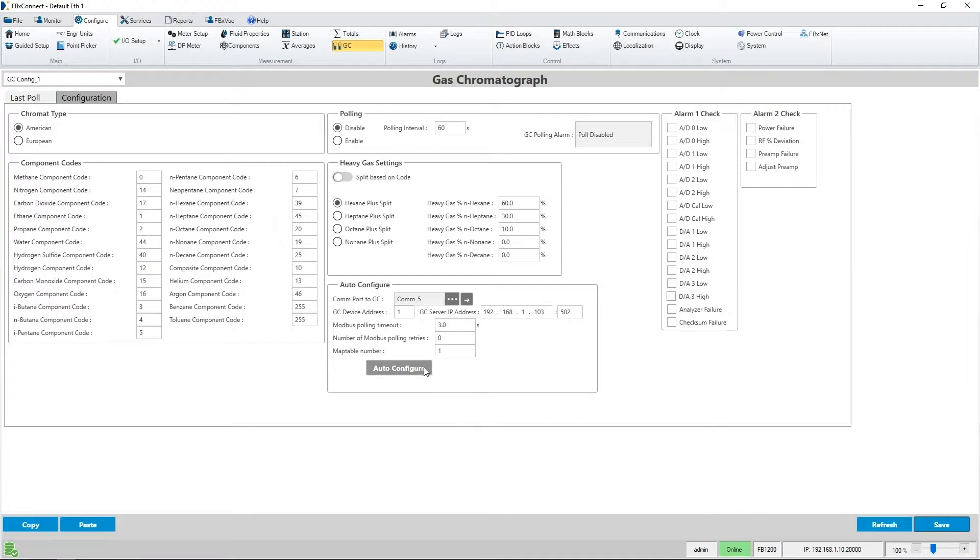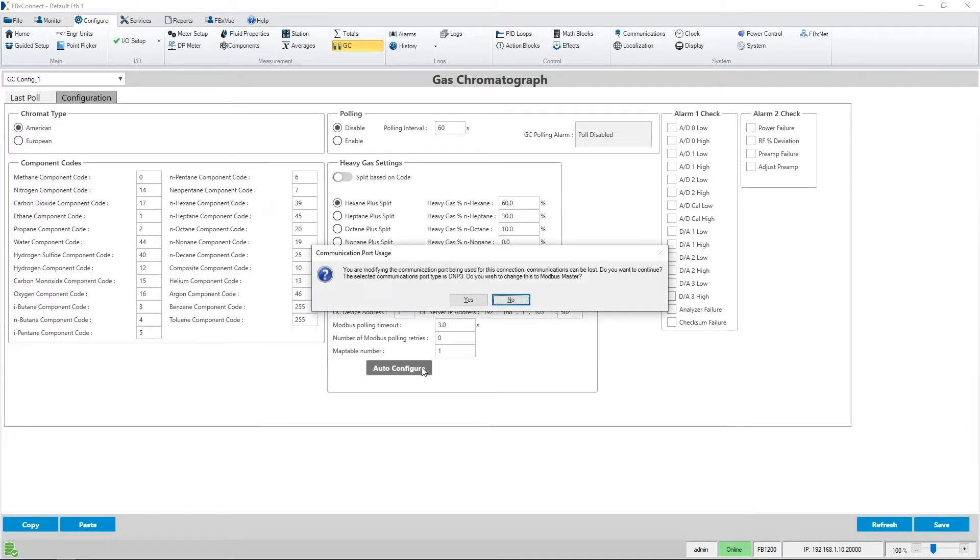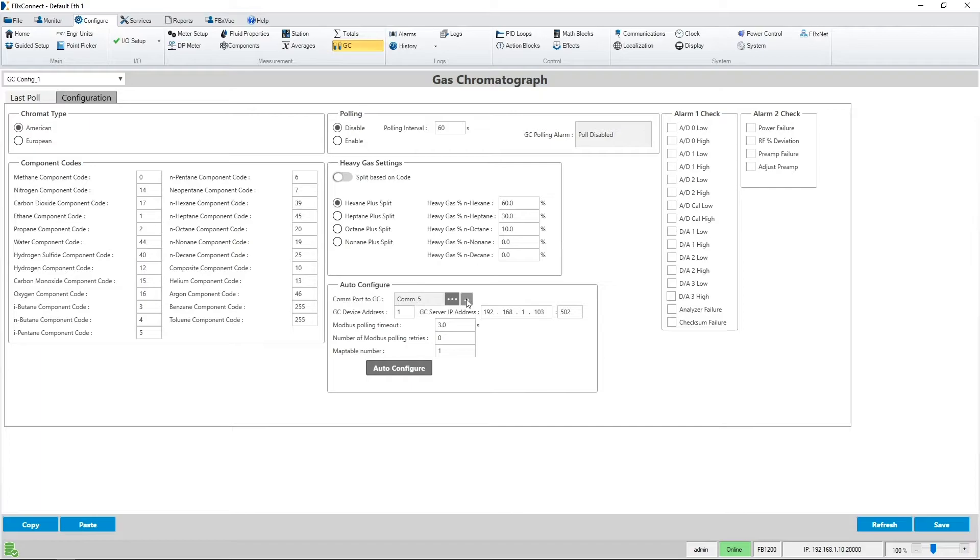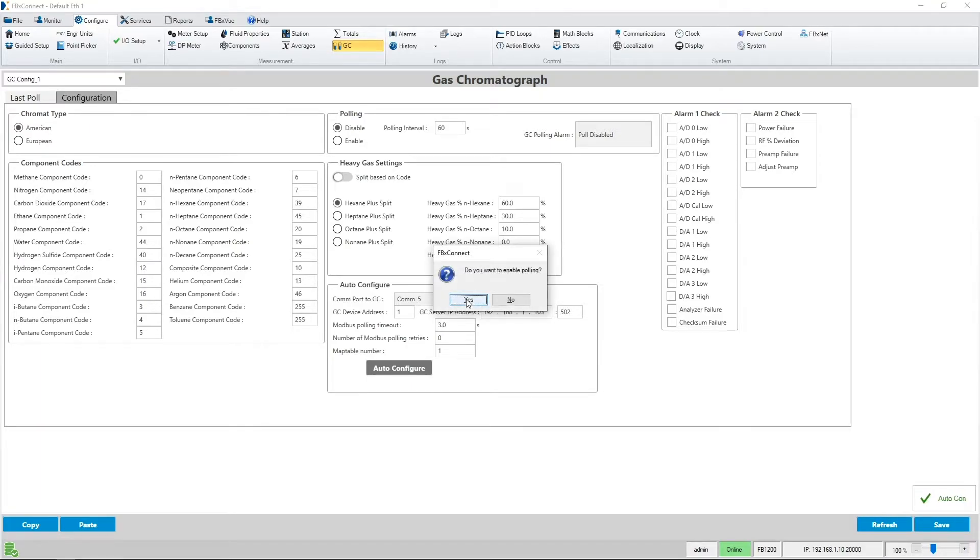Once I do that I can press the auto configure button to set up the GC automatically. A warning message appears as I am also using the same Ethernet port on my FB1200 to connect with FBxConnect. I can safely hit yes here as there's an open session on the Ethernet port. I will also press yes to enable polling immediately.